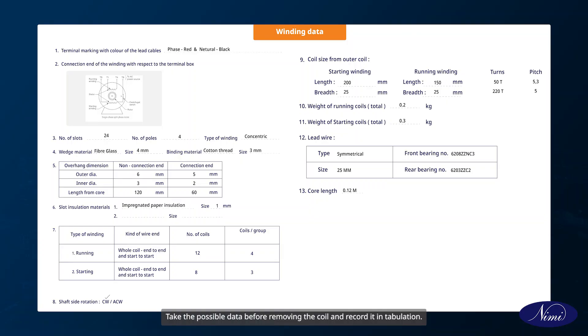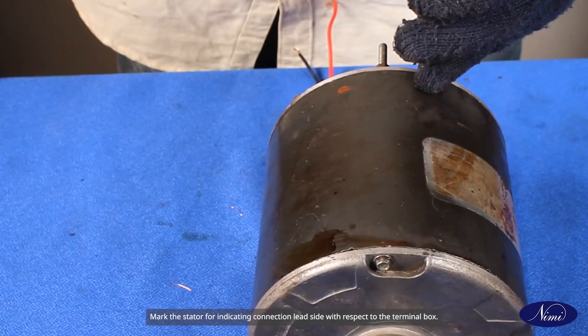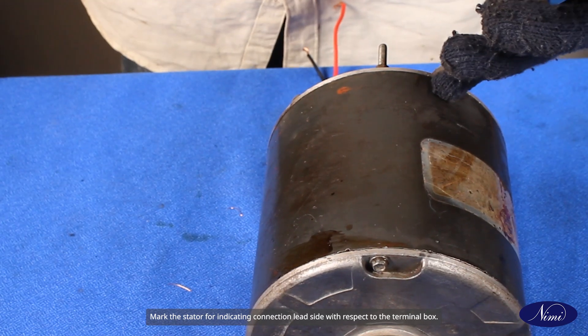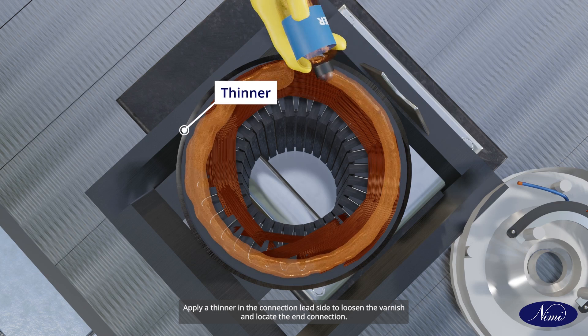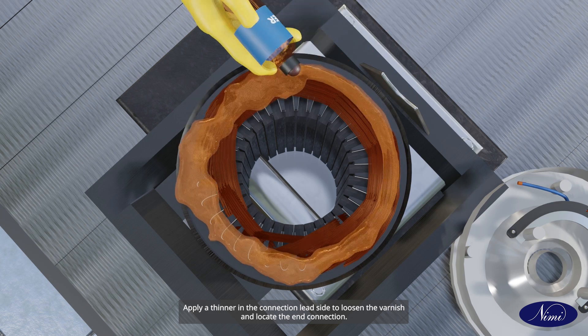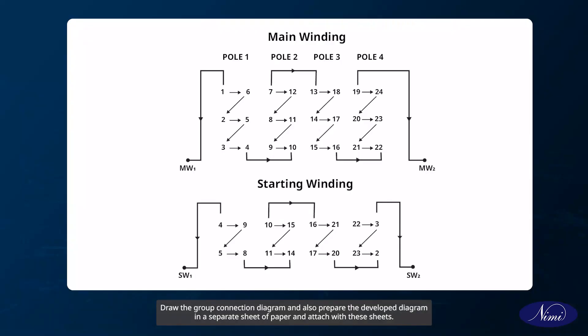Take the possible data before removing the coil and record it in tabulation. Mark the stator for indicating connection lead side with respect to the terminal box. Apply a thinner in the connection lead side to loosen the varnish and locate the end connection. Draw the group connection diagram and also prepare the developed diagram in a separate sheet of paper.